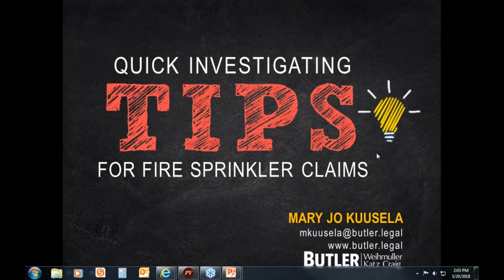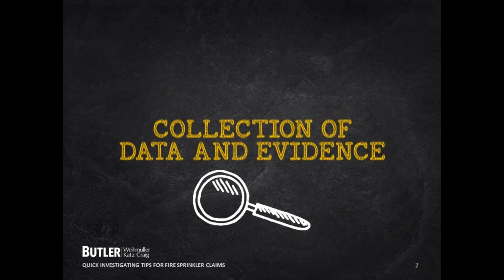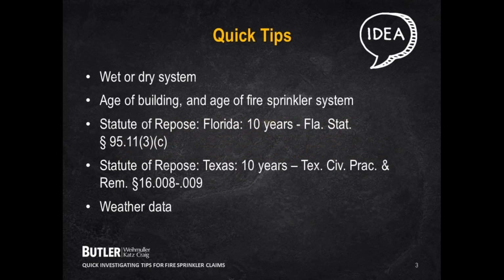for your company. One of the two key factors to look at in the subrogation investigations, I think, is the age of the systems as well as the location where your property loss is located at. So we're going to need to collect some data early on. You also want to know right away whether the pipe involved is a wet or a dry system.